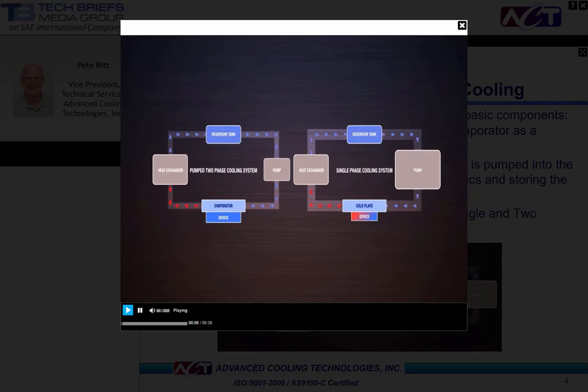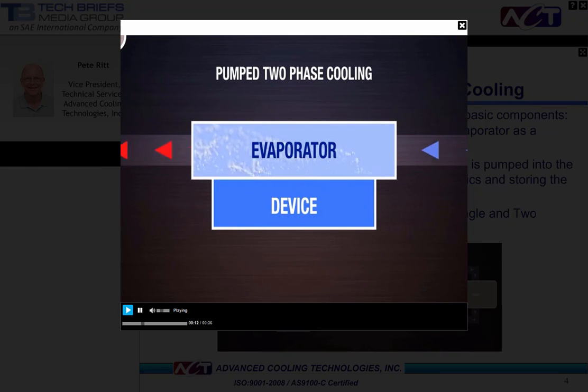Pumped two-phase, or evaporative cooling systems, use the same basic system-level components as the pumped single-phase system. However, pumped two-phase systems typically use refrigerants as the working fluid.